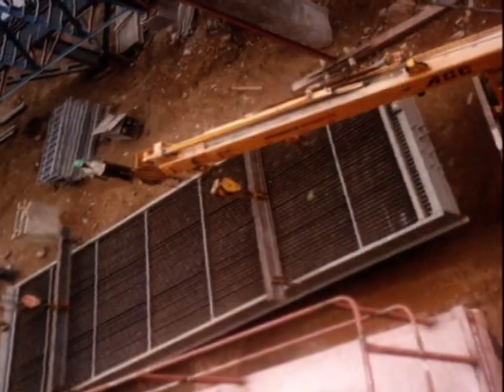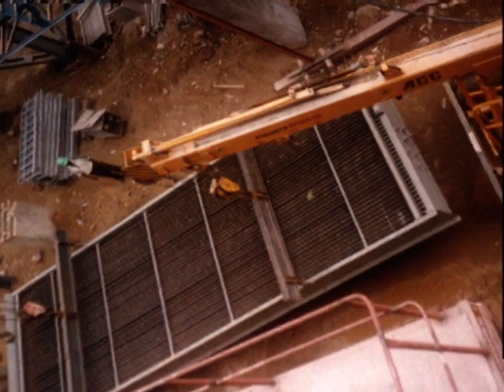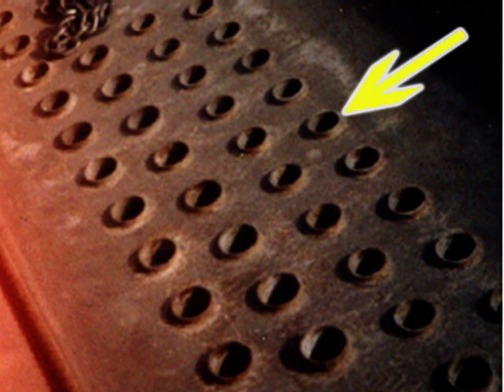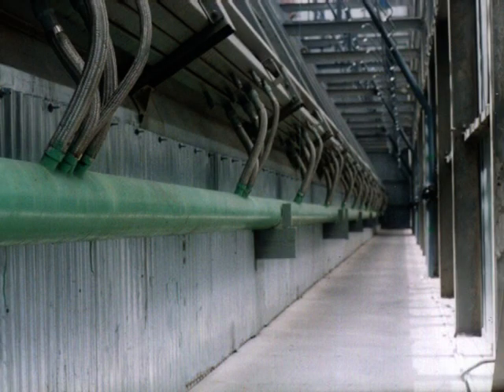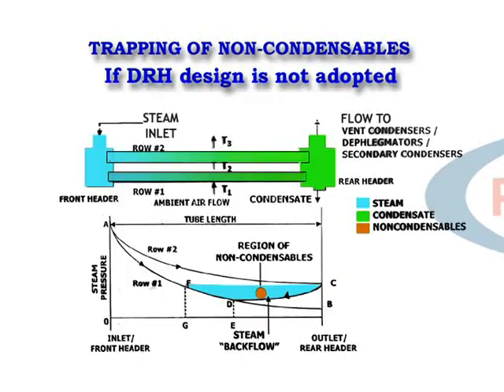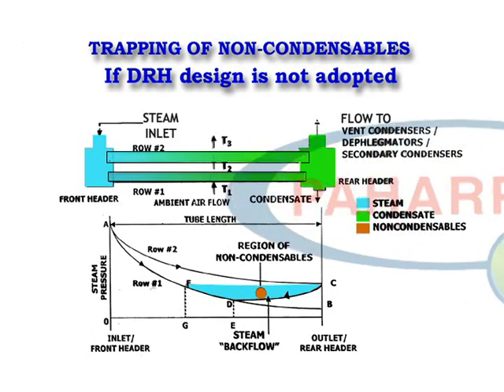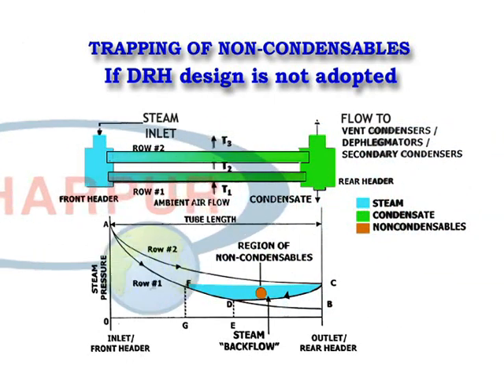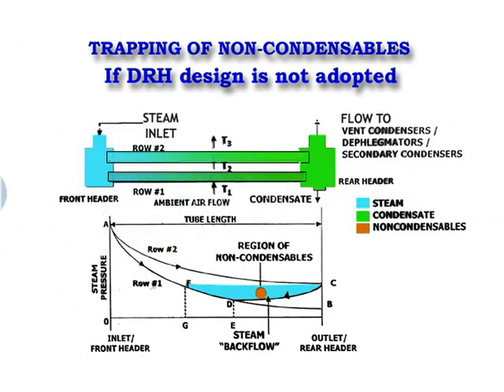The different condensing capability in each tube row is attained by providing two 1.5-inch diameter tube rows at the bottom where large condensation of steam occurs and two 1.25-inch tube rows on the top. The Paharpur DRH type condenser offers the following advantages over other available designs. 1. Due to separate evacuation of each row, the chance of vapor locking and formation of dead zones is eliminated.